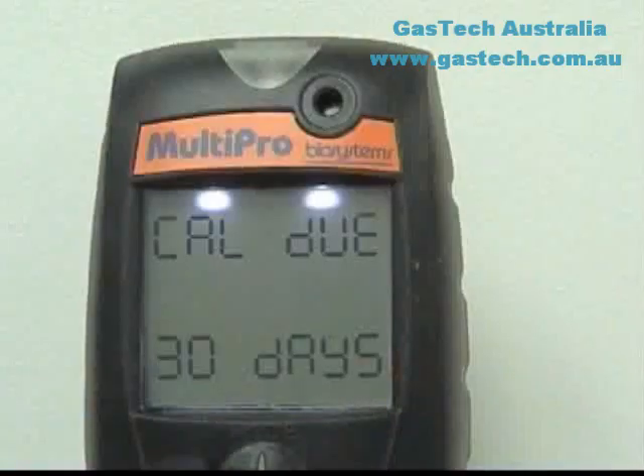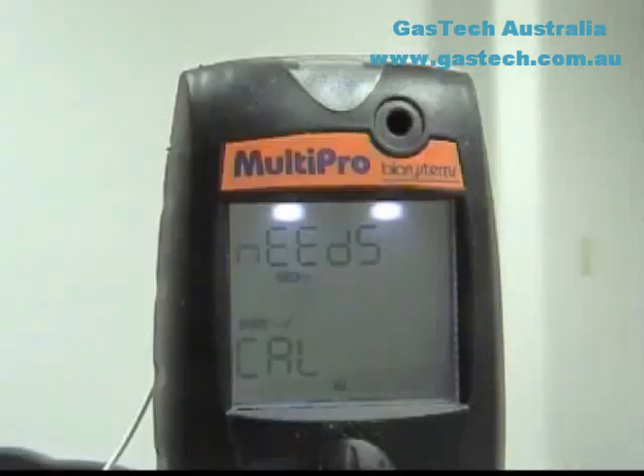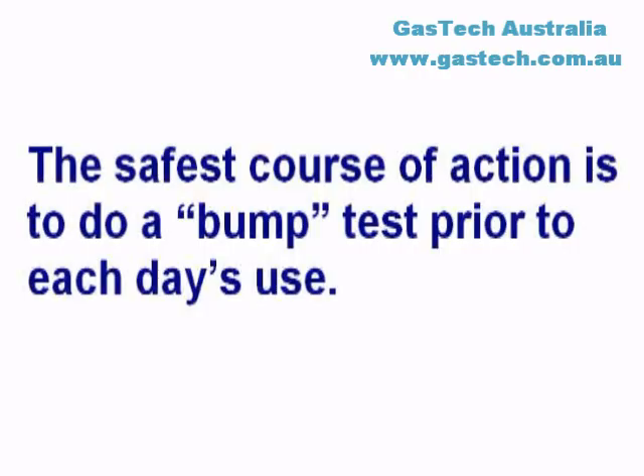All Multipro gas detectors feature a calibration reminder that is shown when the instrument is turned on and can be set to specific intervals between 0 and 180 days. Biosystems recommends that sensor accuracy be verified frequently. The safest course of action is to verify sensor performance daily. See Appendix B of the Multipro Reference Manual for official calibration recommendations.